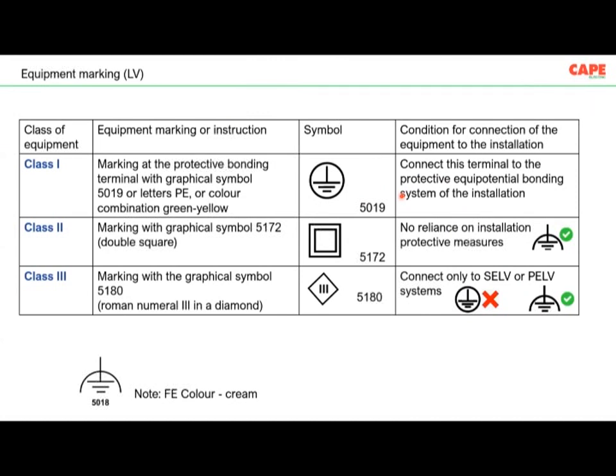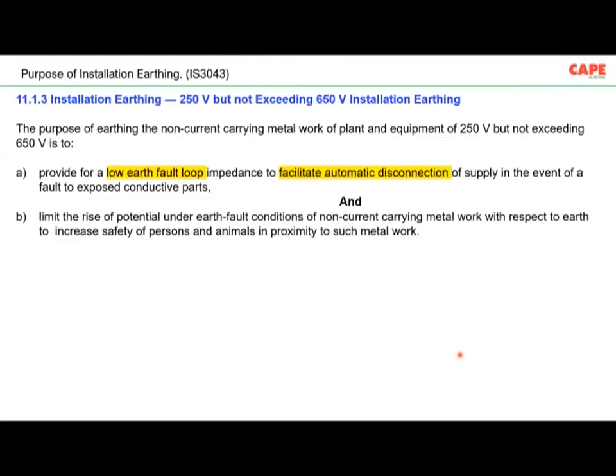Now, functional earthing is a subject in which communication or electronic equipment are connected in such a way that they are able to function very well under normal conditions, or under a fault, or under a lightning condition. That is a different subject. But our main focus today is about safety. IS 3043, clause 11.1.3, what does it say?